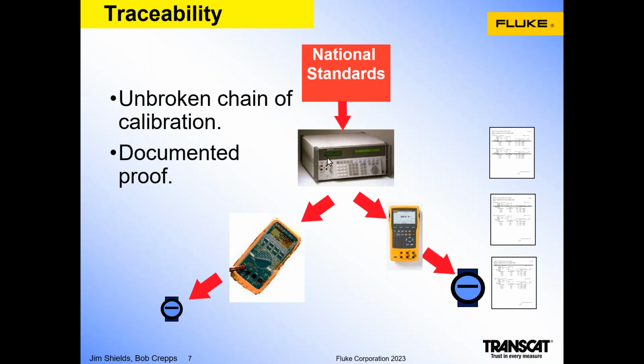Now that bench calibrator can then be used to calibrate different types of field devices. For example, a multimeter, or in this instance, a documenting calibrator. When that calibrator is calibrated by the bench calibrator, there's again another document that represents its calibration information. The serial number of the calibrator used to calibrate that calibrator is recorded, who did the work, its before adjustment information and after adjustment information is all recorded. And that becomes the traceability calibration information of that device.